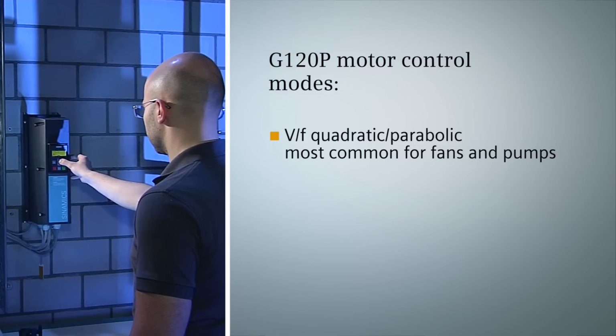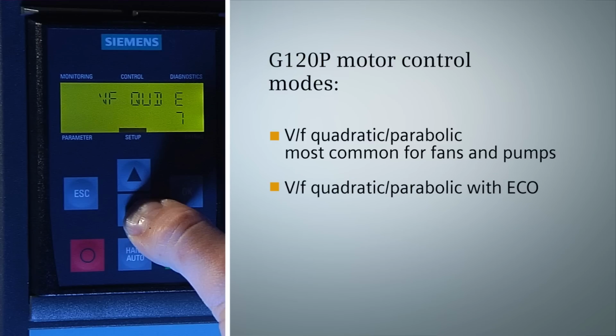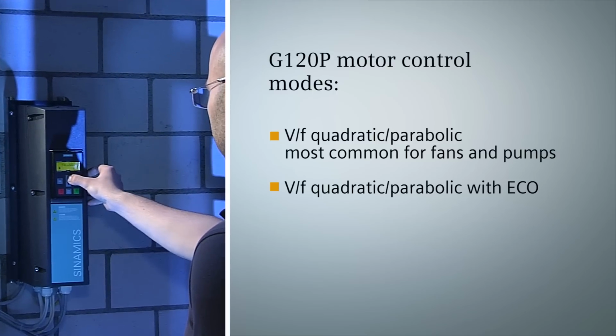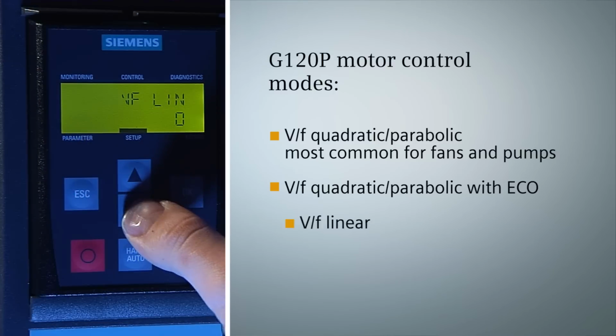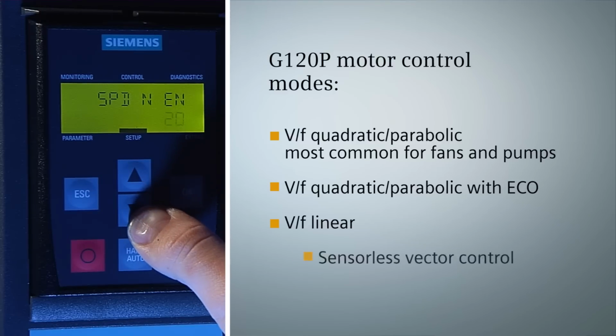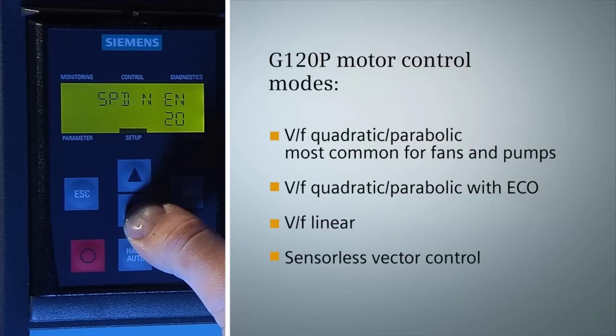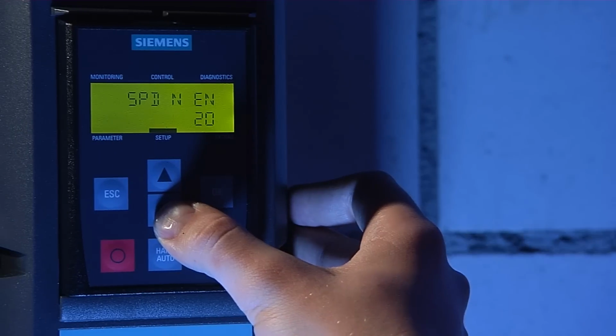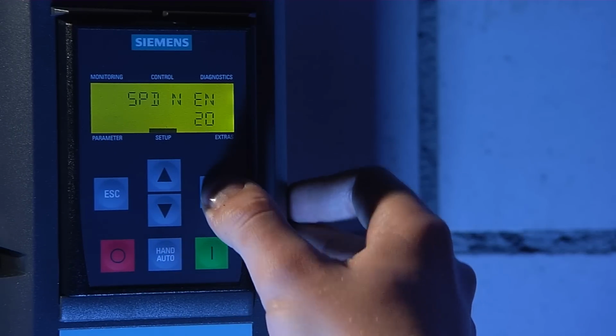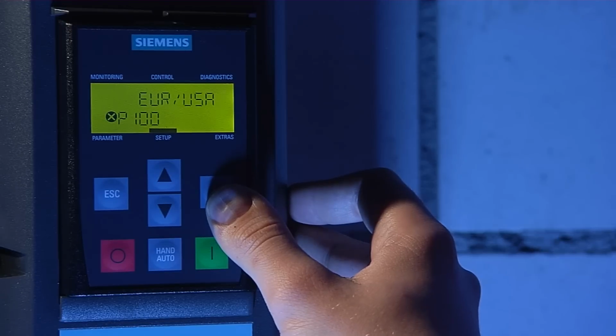There is also an option for V/f parabolic with Eco mode, which helps you to save more energy by reducing the output voltage as much as possible without reducing the motor speed. Furthermore, G120P also supports V/f linear and sensorless vector control. Sensorless vector control is the preferred choice for very dynamic applications or low torque monitoring applications. Confirm by pressing OK. For all motor-related data, please refer to the motor's rating plate.